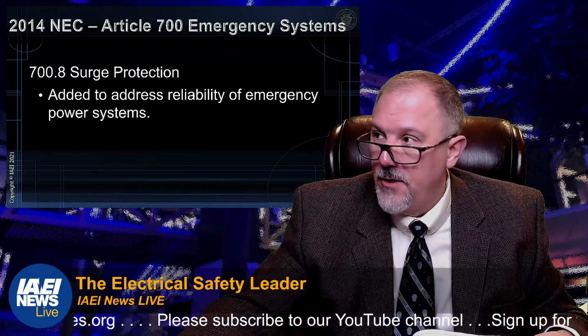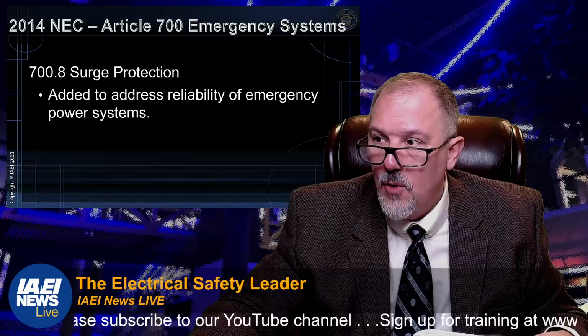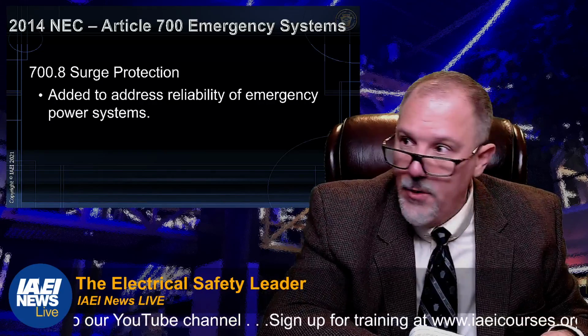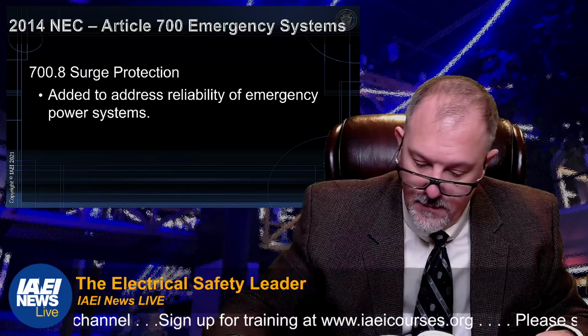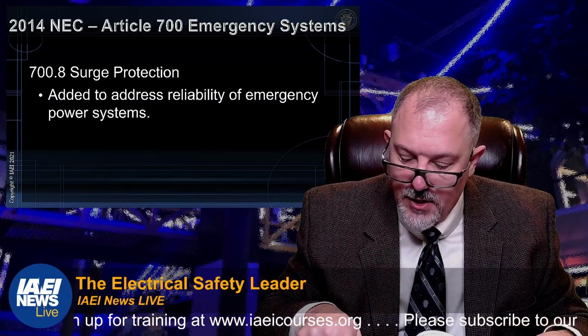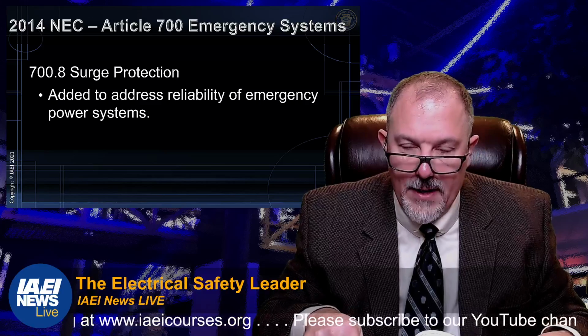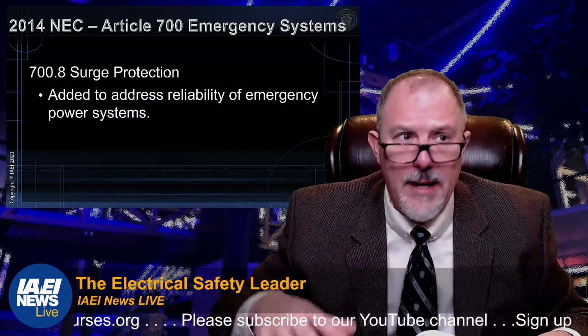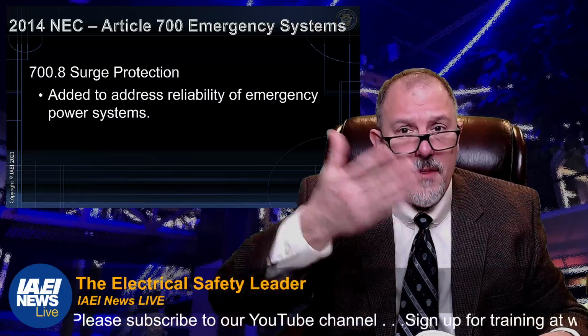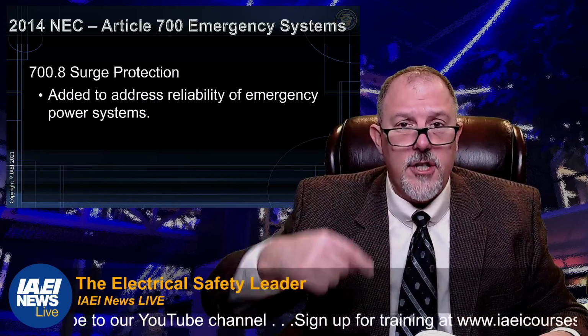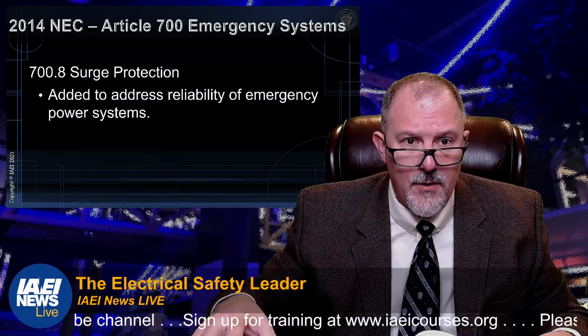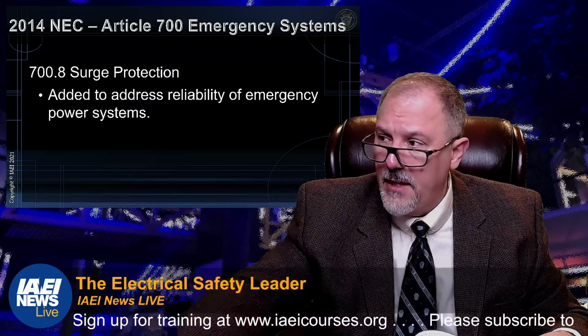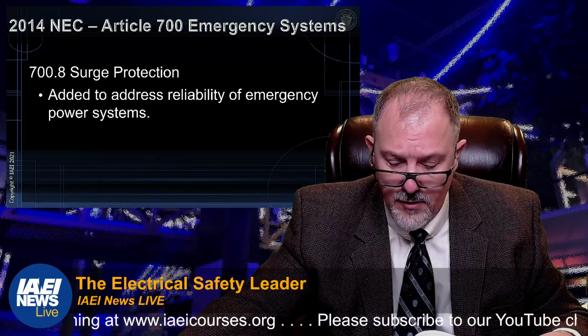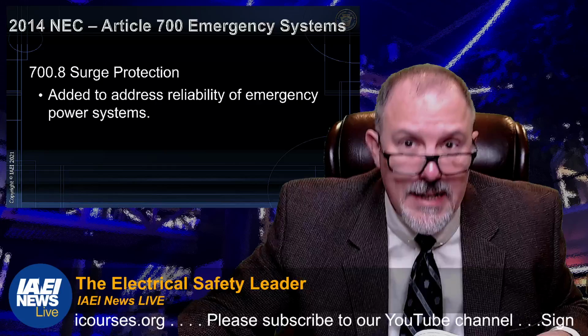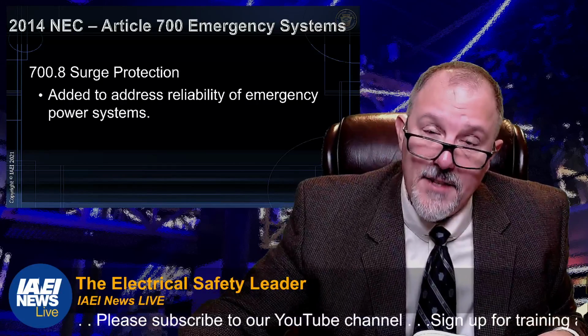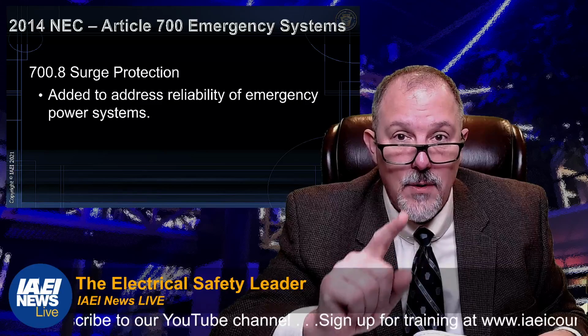In the 14 code, Article 700, 700.8 was added, surge protection. So 700.8 was new in the 14 code. A listed SPD shall be installed in or on all emergency systems switchboards and panelboards. The big question that came out there is, why do I need to put them in every one of them? And I hope you understand the layering effect, that surges can occur within a power distribution system at any one of those levels, and we want surge protection at each of these panels inside of an Article 700 system because we're protecting sensitive equipment that is used for life safety. But again, I don't need them just for life safety.